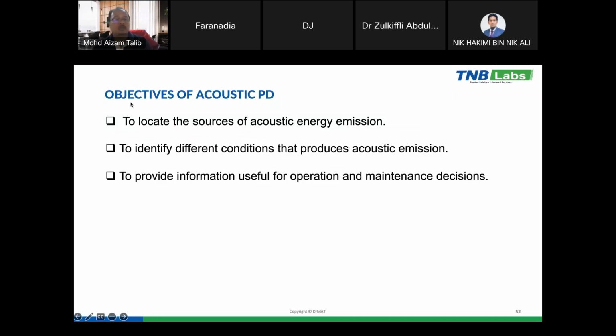So mainly the objective of the acoustic PD is to locate the source of the sounds, and then to identify under what condition it will produce this acoustic emission, whether during high load, high temperature, or during the operation of the tap changer. It provides more useful information for operation and maintenance decisions, especially when the asset owner does not need to untank or open the transformer. So through this PD measurement, we are able to pinpoint the exact location of the faults.